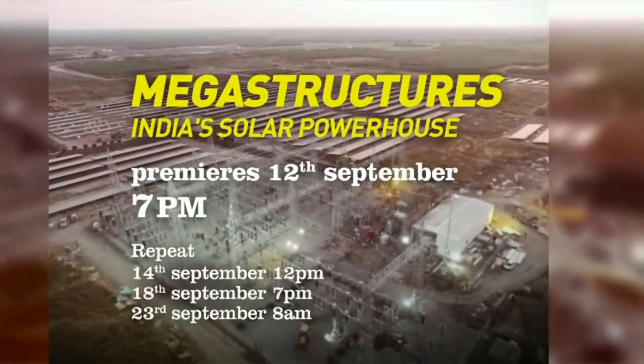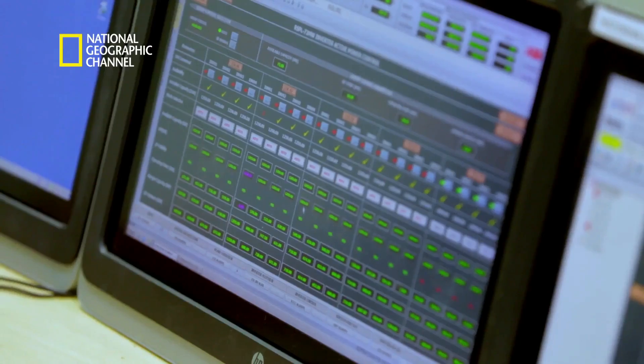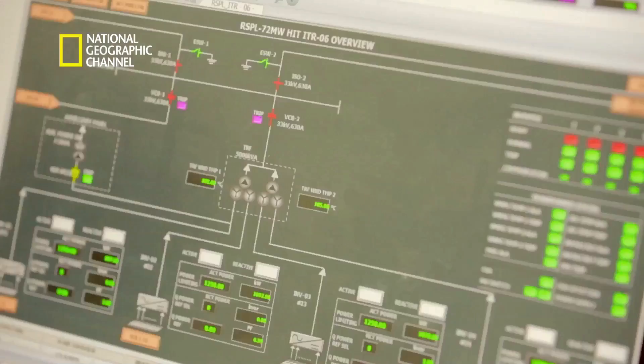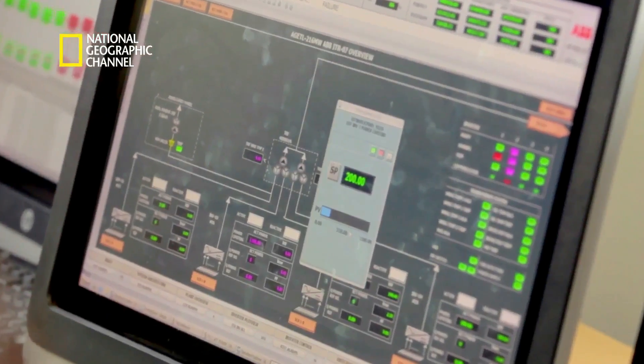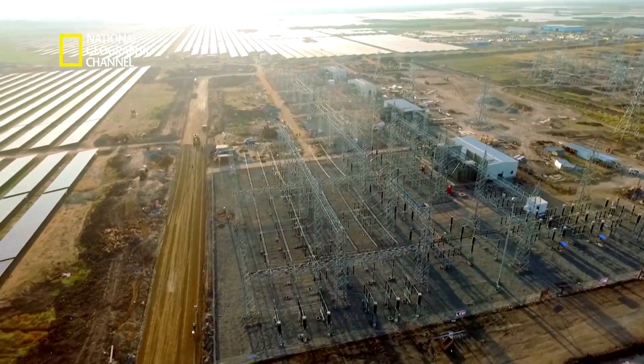This is an inside look at a mega structure that is India's solar powerhouse. A SCADA system was installed for a particular feature — internally called the control philosophy — which will allow limits to be set remotely on power generation, instead of field engineers being sent on site to turn down inverters according to the grid's demand.